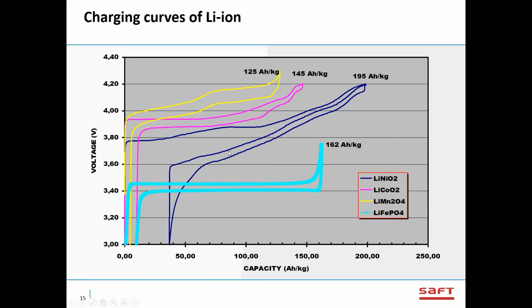This does make the BMS, the battery management system, more complex for iron phosphate because we can't measure the voltage and tell you what the state of charge is. We can, when it's very close to empty and it starts down the steep curve, or when it's very close to full, we can tell what the state of charge is. But in the middle, it's very flat. And so what we do is we measure the current with a current sensor, and we count the amp hours during a discharge or during a charge to tell you the state of charge. With metal oxides, it's easier because you can just measure the voltage and you can tell where you are on the curve.